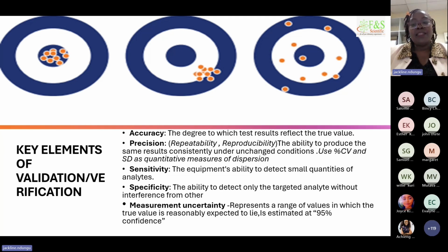And as I have said, we can sit here the whole day just trying to do measurement uncertainty. The requirement, as per accreditation standards for those who are accredited, is that you do it at least when you're doing your initial verification. It's also required when there's a major preventive maintenance that has affected maybe the operation of that instrument, then you can do another uncertainty of measurement. But once you have done it, you can basically stay at that.